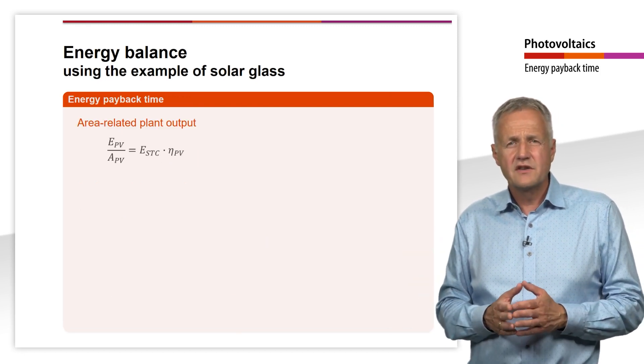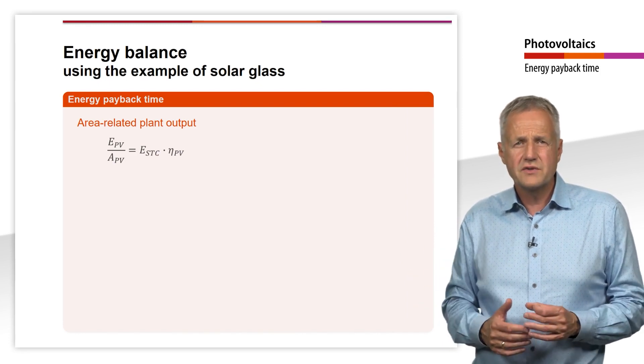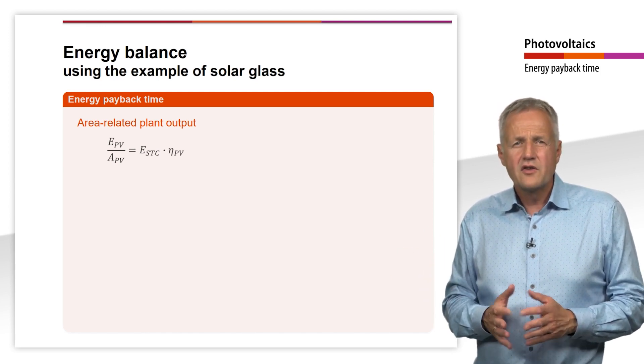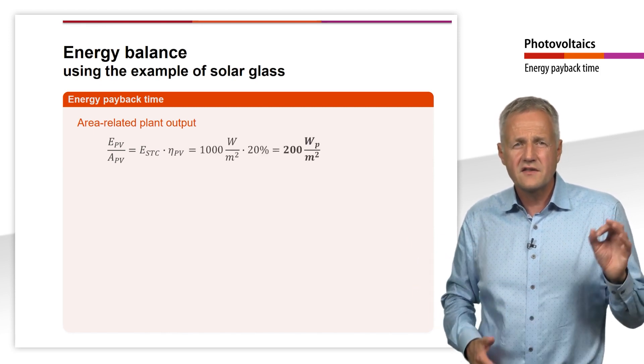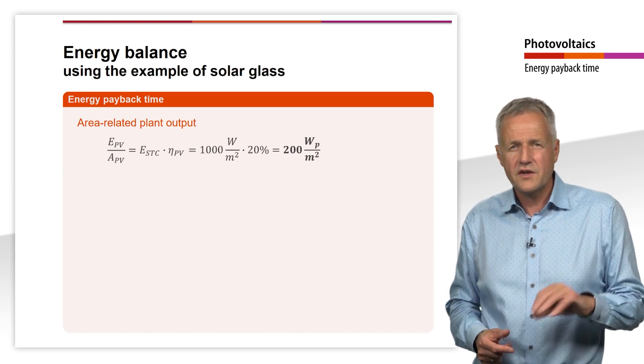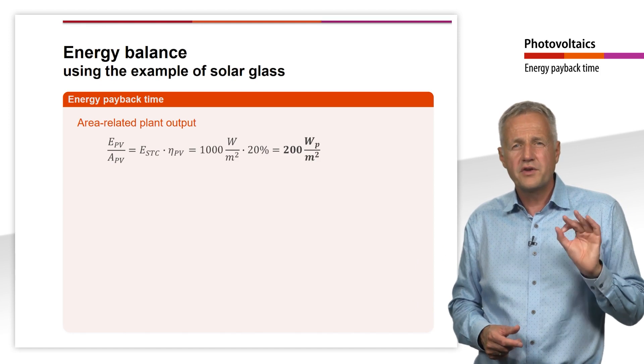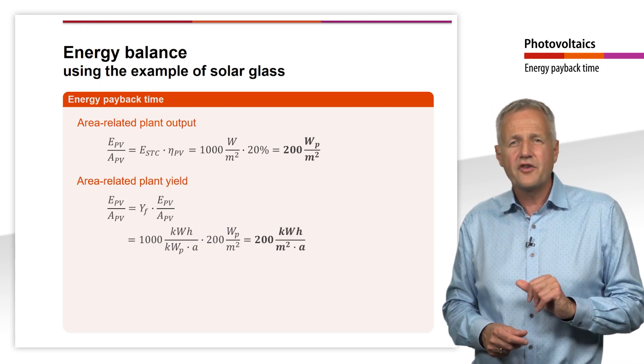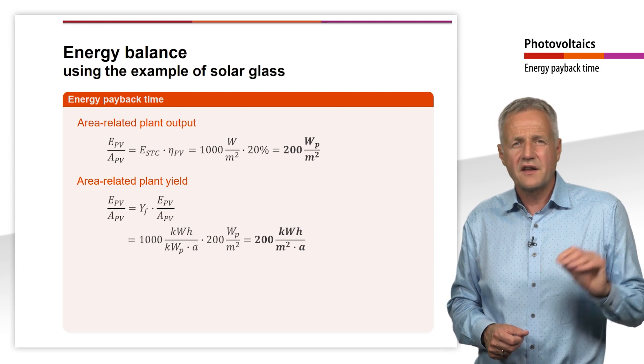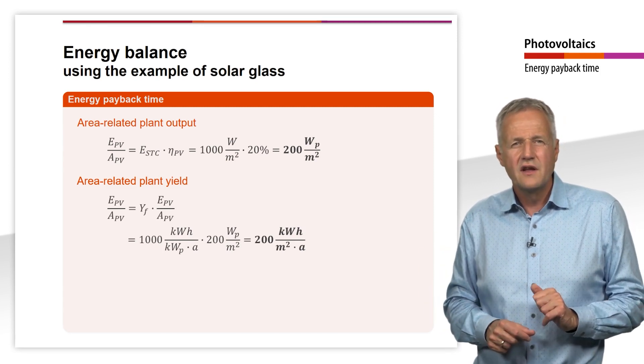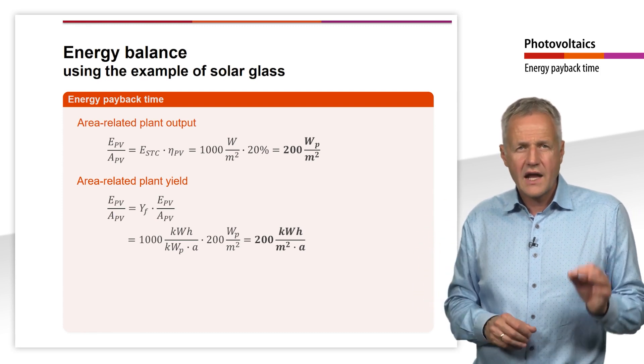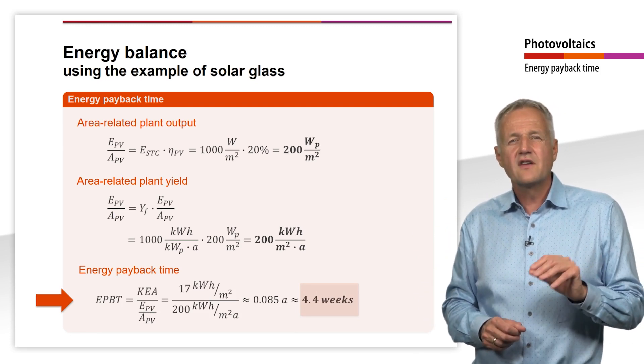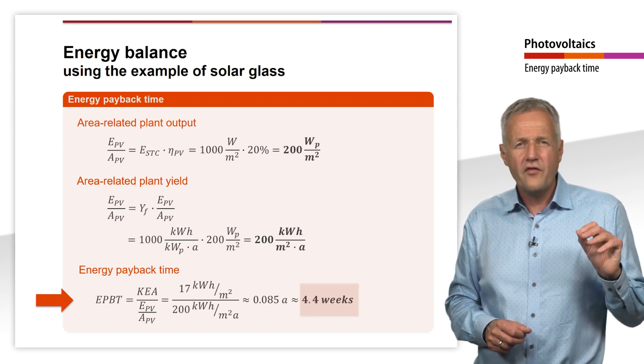To calculate the payback period, we also need the energy yield of the PV system in which the solar glass is installed. We consider a plant in southern Germany. We assume a module efficiency of 20%, meaning that the modules at STC — at 1000 W per square meter — produce an output of 200 W peak per square meter. For a plant in southern Germany, we assume a specific annual yield of 1000 kWh per kW peak, so we can expect an annual yield of 200 kWh per square meter. Putting this in relation to the area-specific cumulative energy demand of 17 kWh per square meter, the result is 0.085 years, or 4.4 weeks.